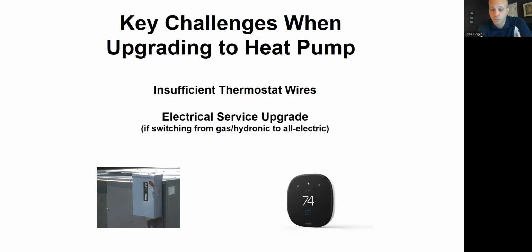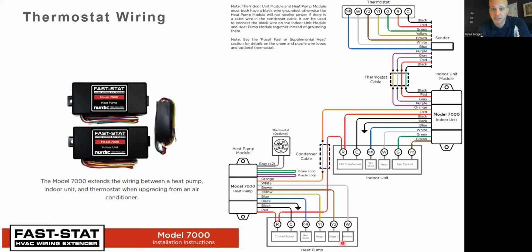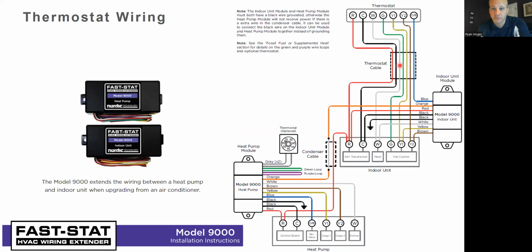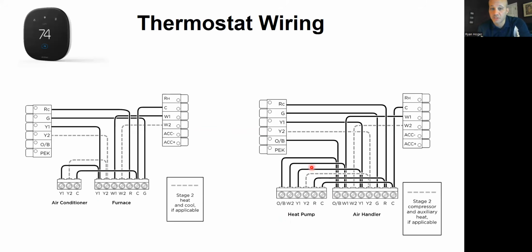Anne asks, what about wireless thermostats? You can use a wireless thermostat. The problem with the vast majority of wireless thermostats is that they are wireless from the thermostat down to the indoor equipment, and they still need wires from the indoor to the outdoor. And that's where you have the biggest quantity of wire need. So you could do that.